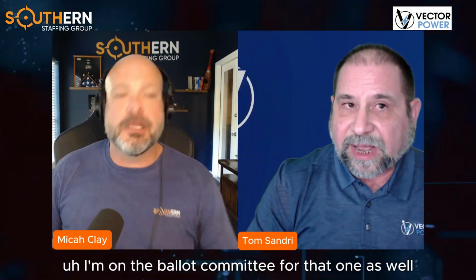Now, the ATS is up for renewal. I'm on the ballot committee for that one as well. We're still working on the 2021 revision of the ATS. It's still the original, where when you get to the cable section, it's like, here's the IEEE 400 document, go read and figure it out. Now, the new ATS is going to mirror a lot of what was accomplished in the recent release of the brand new MTS, where that whole cable section has really grown and blossomed.